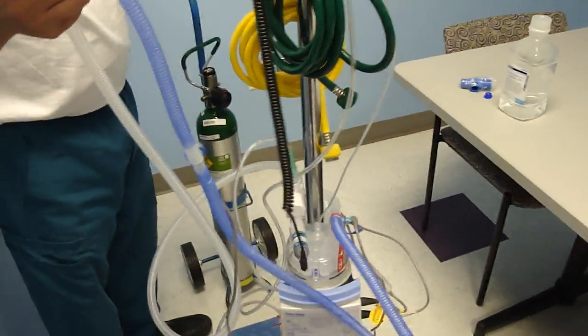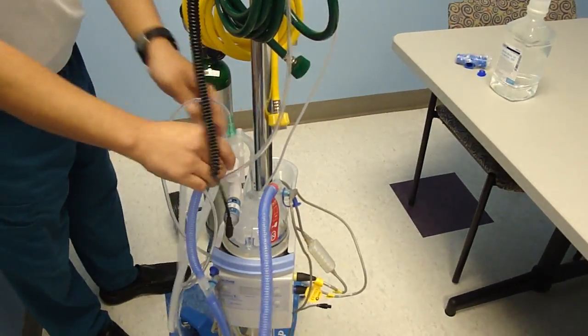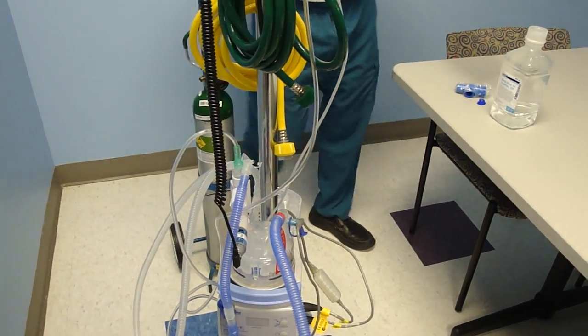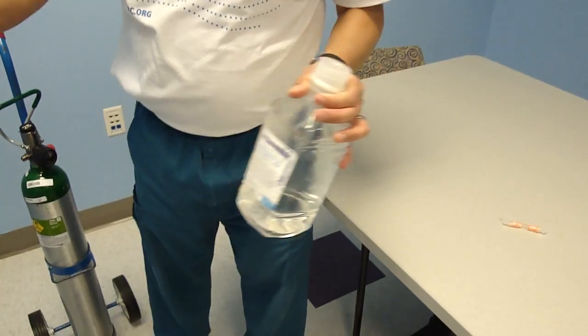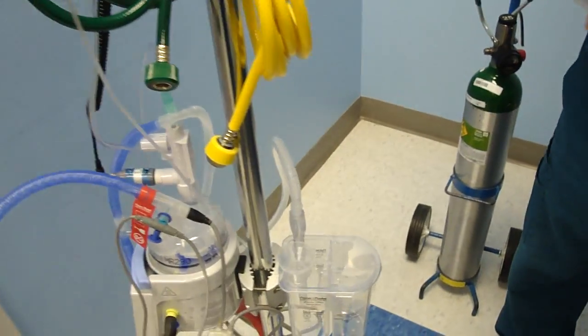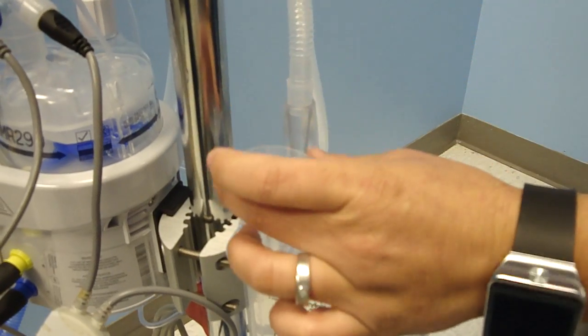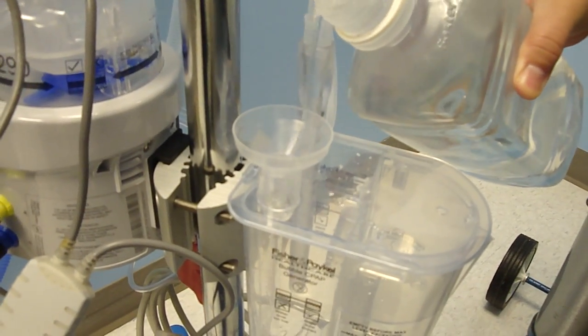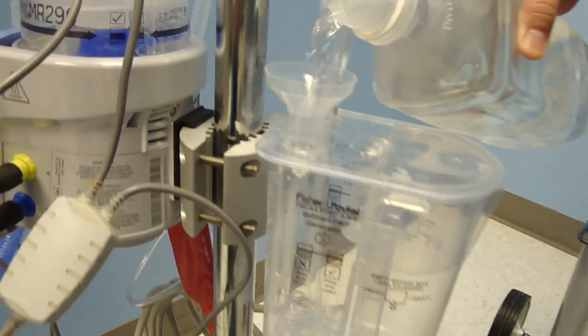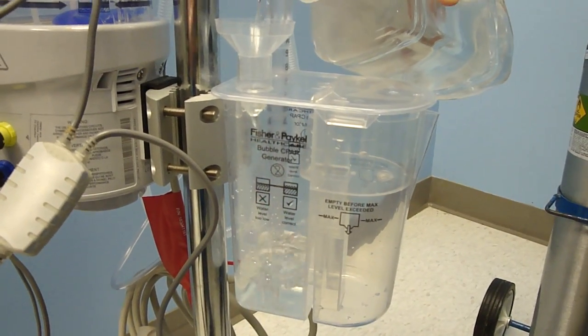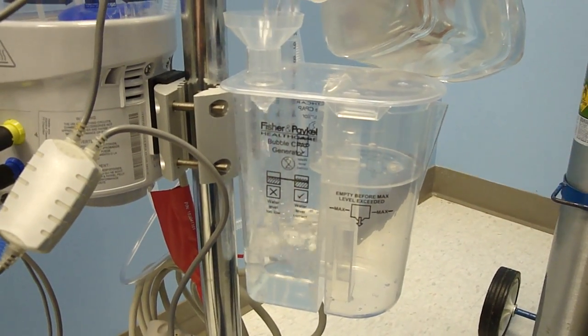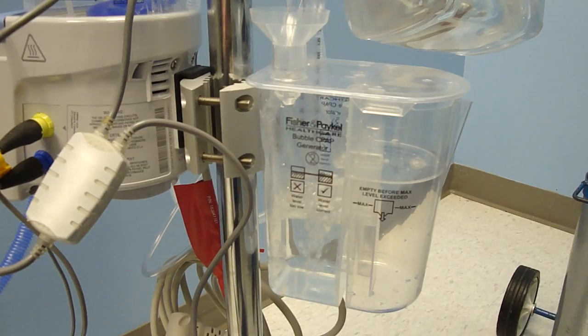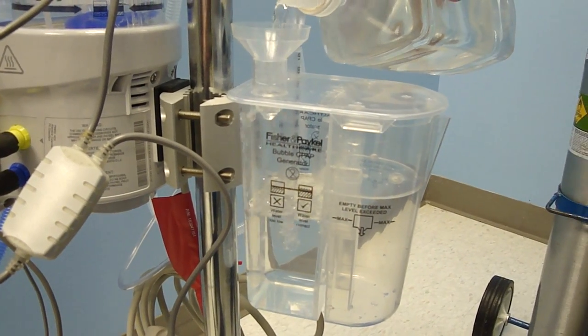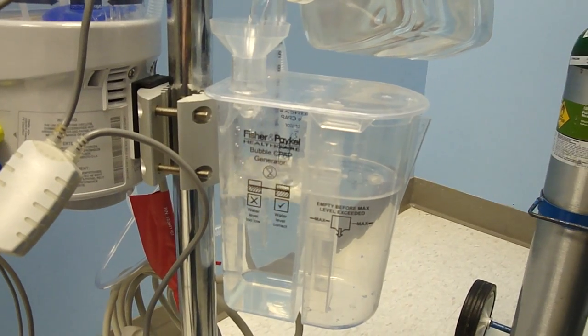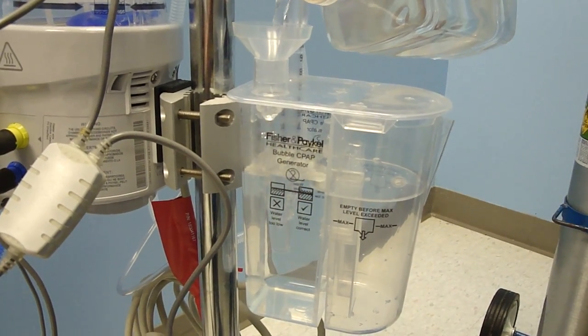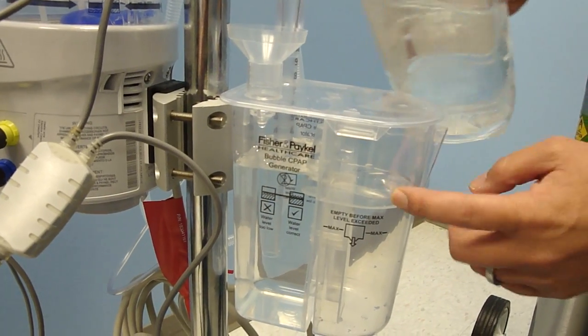Okay, the next step before we can test the system is to add the water. So we use 1 liter of sterile water, and we're going to pour the water into this funnel right here. This funnel is removable. That's where you're going to pour the water. You keep on pouring the water until you see the water overflow to the suction chamber, which is right here. Good thing is no more measuring tape. Okay, as soon as I see water overflow, I stop.